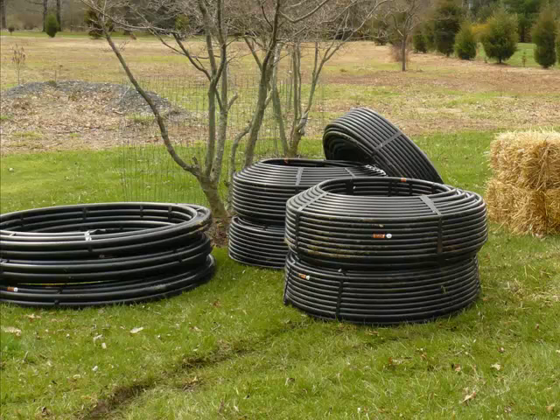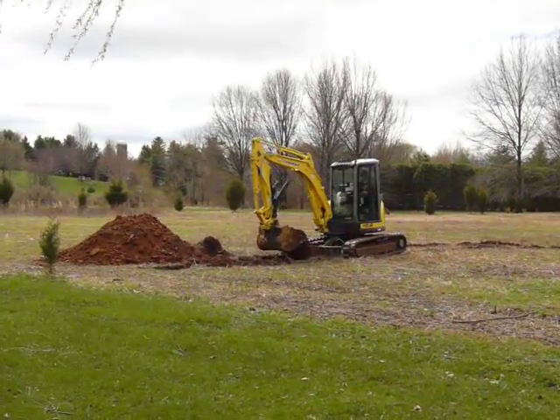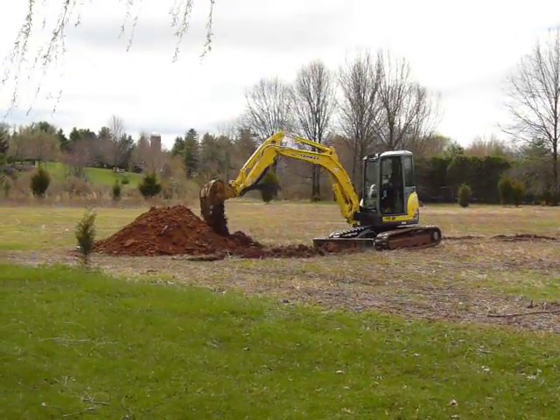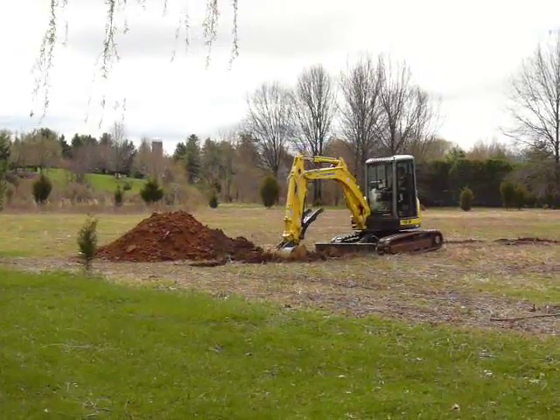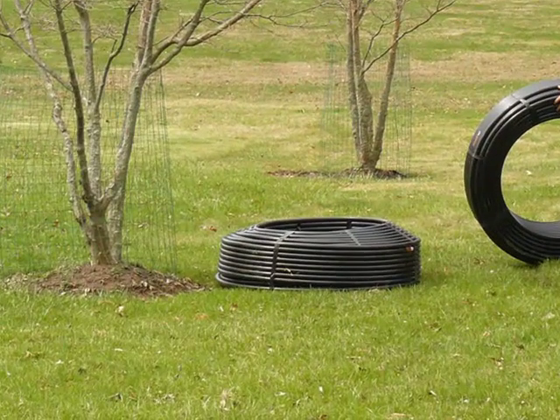The goal is all this tubing — five coils of 800 feet, and the header tubing which you see on the left — has to be dug into the ground. We need to put in four trenches to take all these coils. Once we've determined exactly where the trenches are going to be, the digger has started to dig, digging trenches 100 feet long, three feet wide and six feet deep.